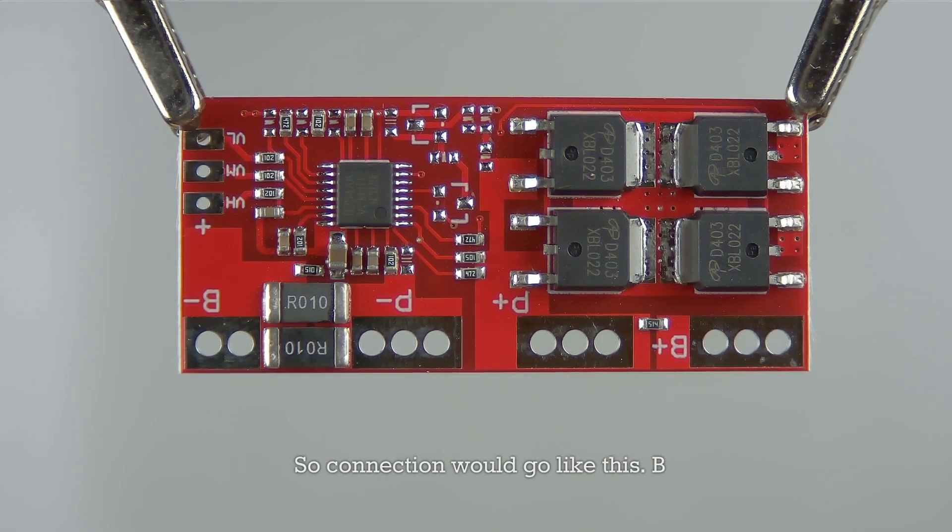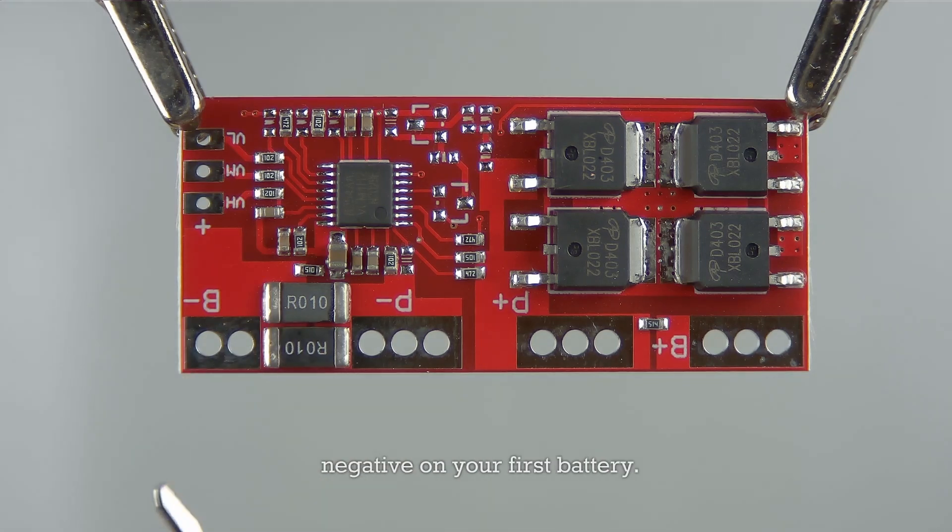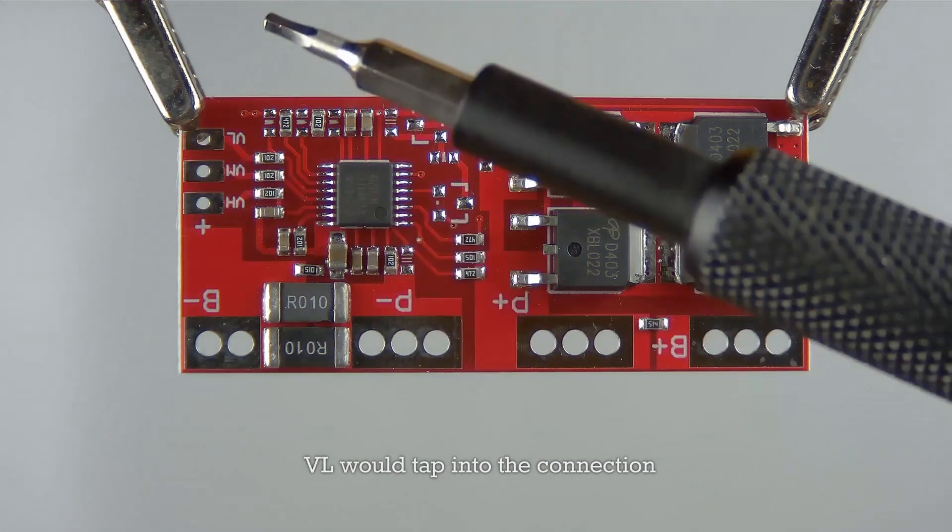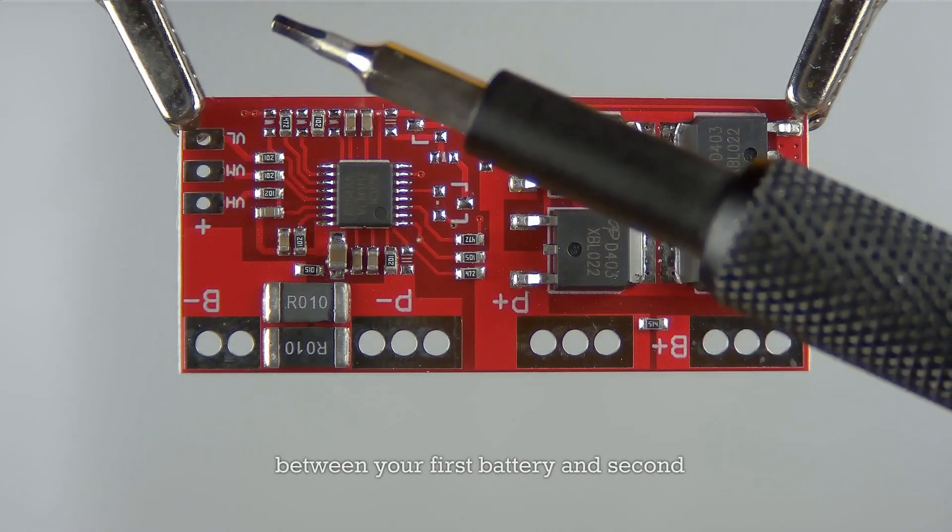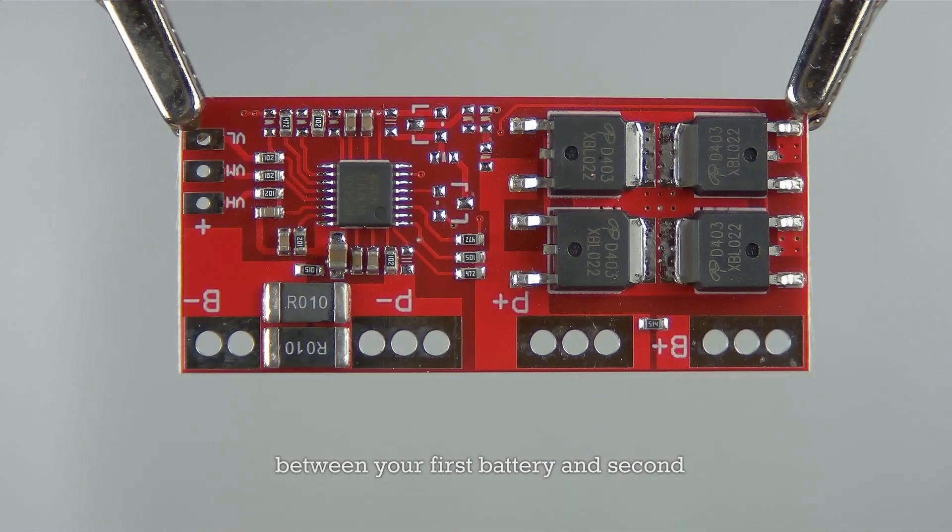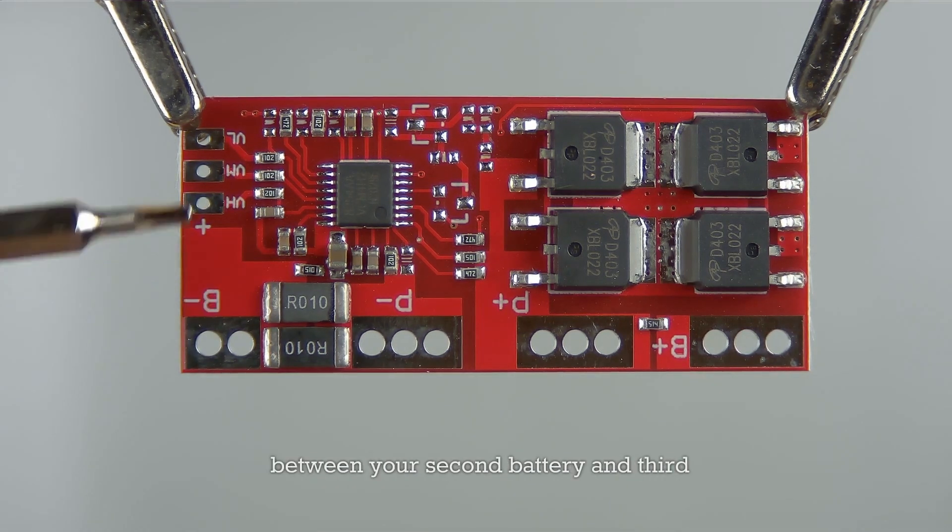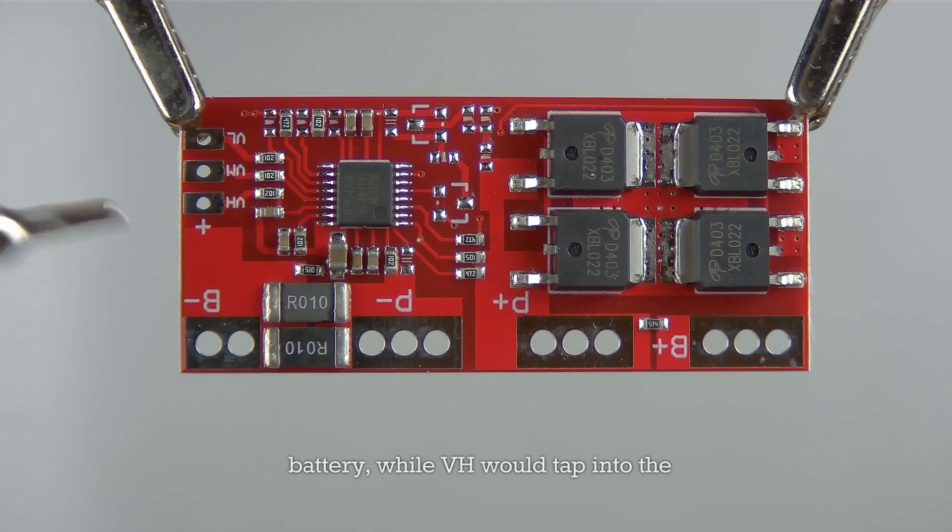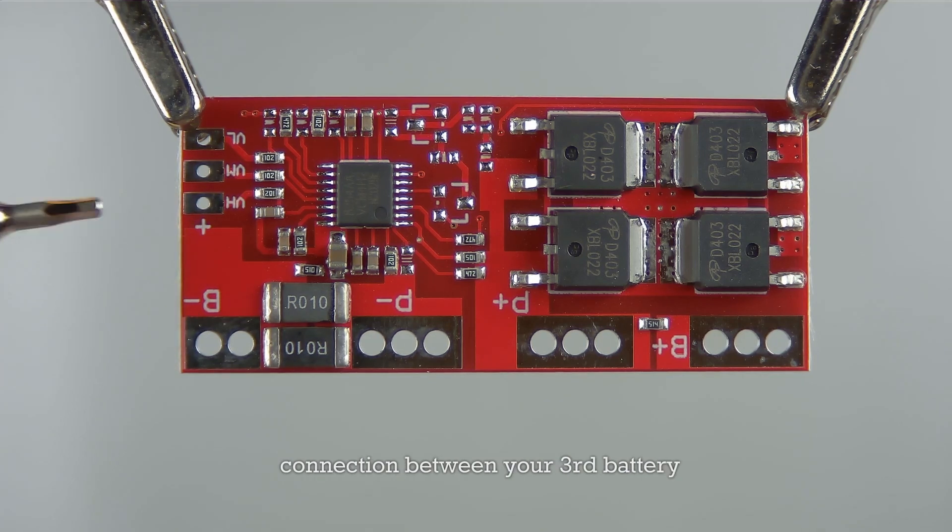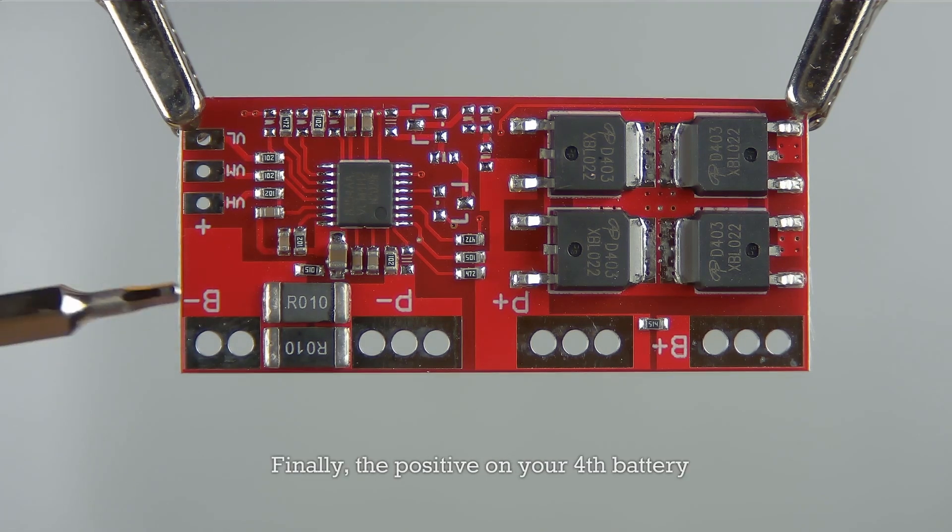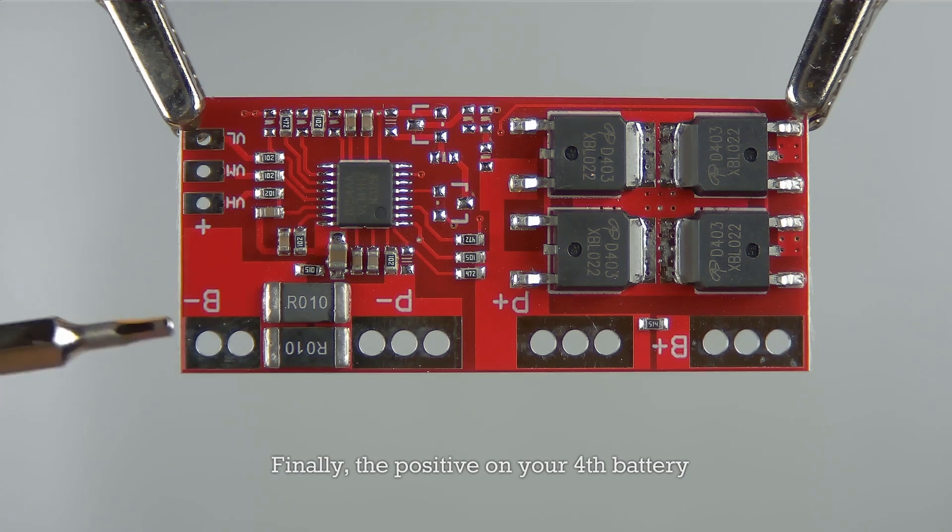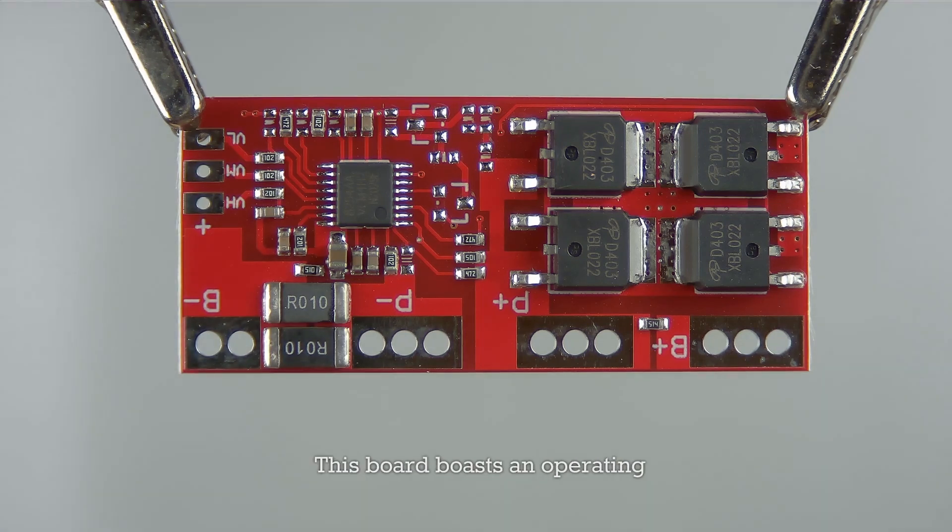So connection would go like this: B minus here would connect to the negative on your first battery. VL would tap into the connection between your first battery and second battery to monitor the voltage there. VM would tap into the connection between your second battery and third battery, while VH would tap into the connection between your third battery and fourth battery. Finally, the positive on your fourth battery will connect to B positive.